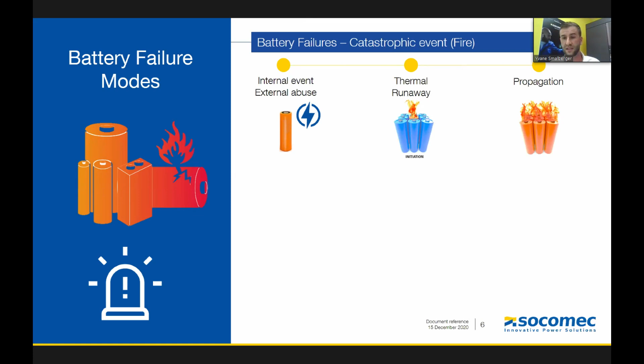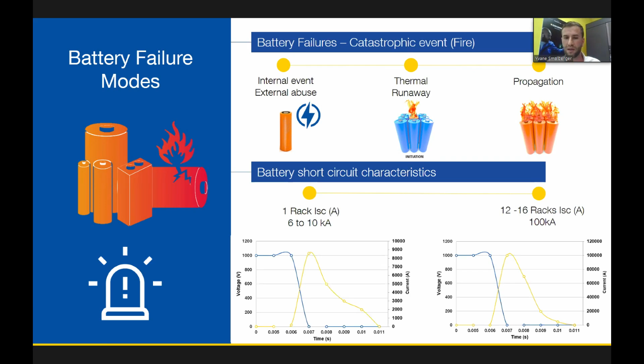Now, if you take into consideration what I mentioned earlier, and you look at 1 rack or even 16 racks, at the point of either of these failures, when we start in the thermal runaway condition, the short circuit indication could be very close to instantaneous, a very short time period where it reaches its maximum discharge. And our system needs to manage this electrical power to be able to ensure that the energy can be maintained. So how do we find a solution to prevent failure modes? There are 3 options. The first one is overcurrent protection. The second one is overvoltage protection. And finally is thermal management. For the purpose of today's presentation, we will focus on overcurrent protection. So I'm not going to cover energetic failures, which needs gas detection, fire detection, or extinction.